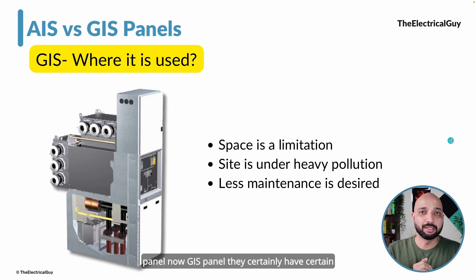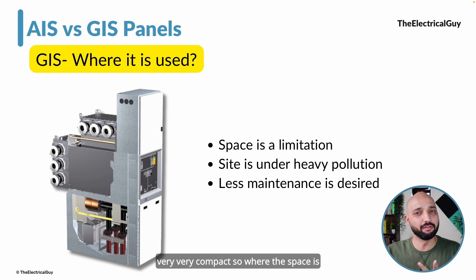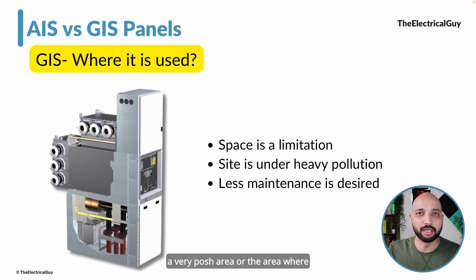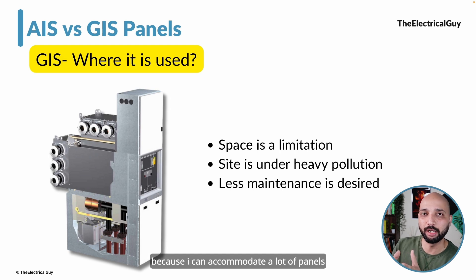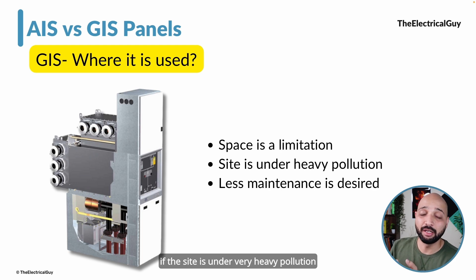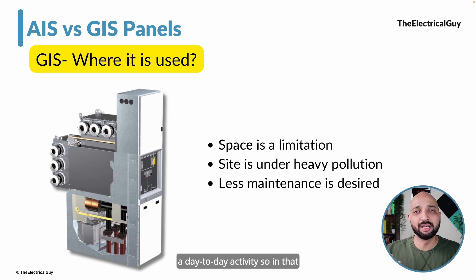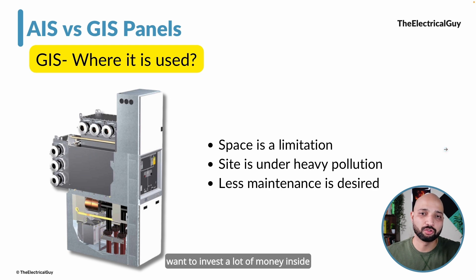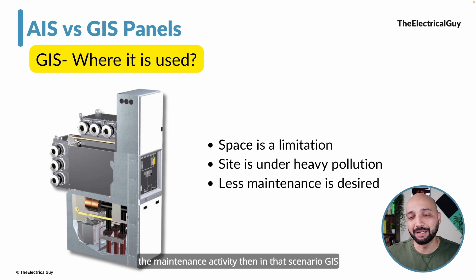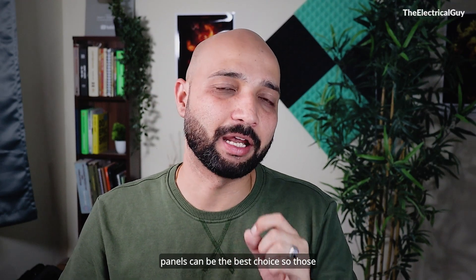GIS panels have clear advantages: they are maintenance-free and very compact. Where space is limited — for example in a posh area with high land rates — GIS is a good choice because you can accommodate many panels in a compact room. If the site is under very heavy pollution, like cement industries, GIS is better because it is sealed and the internal components are not affected by pollution. If minimal maintenance investment is desired, GIS panels are the best choice.